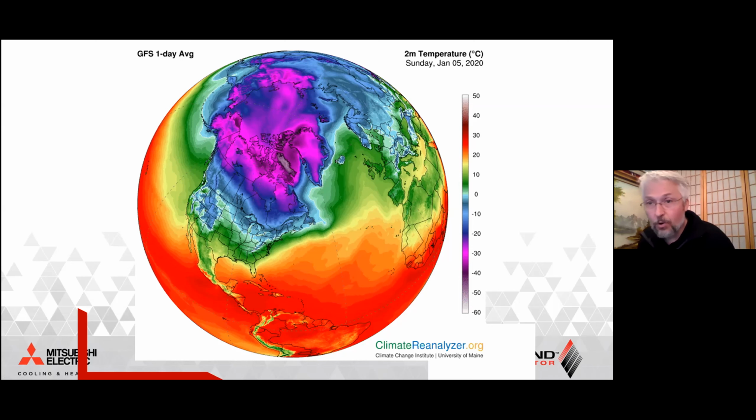Now, of course, with BrightBuilt homes, you have a very tight house. Your heat loads are relatively low, and so you don't even need a whole lot of heat pump equipment in order to accomplish that task. But even if you had a leaky farmhouse, if you applied enough equipment to it to match the heat load for the house, and there are calculations and ways of assessing what the heat load is, you can heat just about any kind of space, even in Maine and New Hampshire, with heat pumps, as long as they're designed to provide heat at cold temperatures, like all the equipment that receives rebates through Efficiency Maine, and that you've selected equipment or a combination of multiple pieces of equipment in order to accomplish the task that you're asking for.